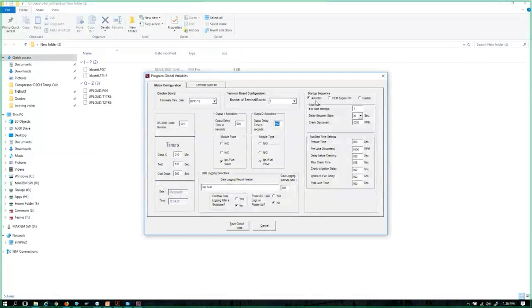Okay. So, auto start, again, was originally created for an old school engine that we wanted to give some automation to. One last thing that I'll add to here, the only way to trigger this system into this auto start sequence is by triggering the remote reset, momentarily either opening or momentarily grounding the R terminal on the primary terminal board. So what happens if you push reset at this point on the face of the DE-3000? The answer is the startup sequence will not occur.